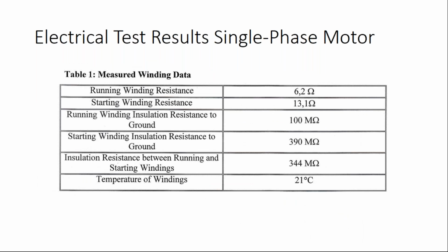Leaving the vibration analysis, I just looked at some of the winding data. These are relatively simple machines, and you see for the capacitor start motor, these are the measurements I did. I looked at the temperatures, and then looked at the winding data, and then went back to the standards.